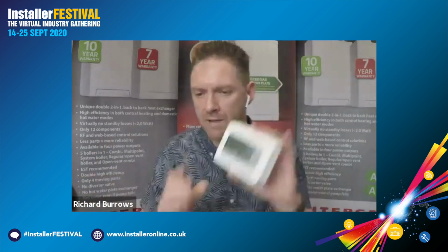So if we go from something like this and come over to the new wave of controls, like the T4 - T4 is what we call a Class 5 control. The T4 control basically allows the boiler to adjust its flow temperature. So instead of being 75 degrees all the time, the controller can work out the heat loss from inside the building. Where we'd use weather compensation, which we'd classify as an ERP Class 6 control using an external air temperature reference, what these Class 5 controls do is learn the inside warm-up and cool-down periods of the building, and adjust the flow temperature of the boiler to suit the heat loss it can see and the way the rooms heat and cool.